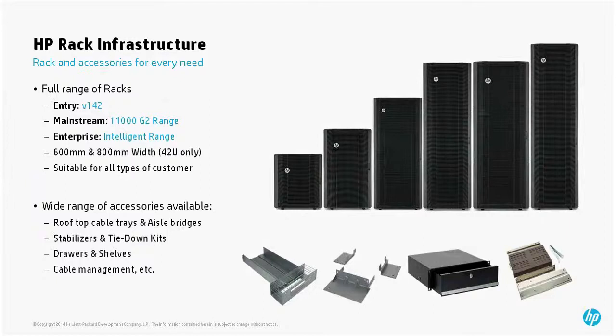And I have some more specifics on this stuff, and of course we have a wide range of accessories, everything you would expect. Filler panels are really important. You guys know all servers are designed to cool from front to back, and if you have gaps in the rack it's going to cause airflow issues. So wherever there's not a server or something else in a U space, make sure you put filler panels in there. You guys know this stuff, this shouldn't be anything new.